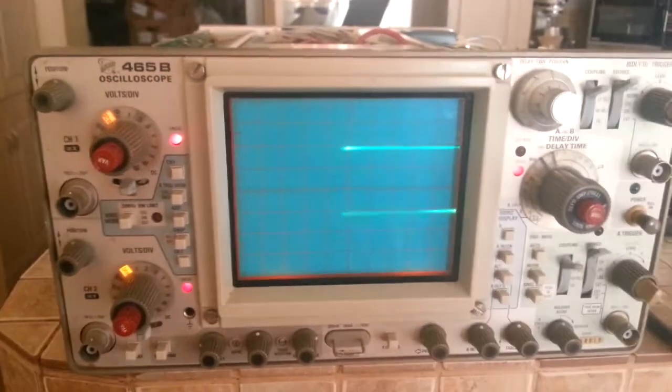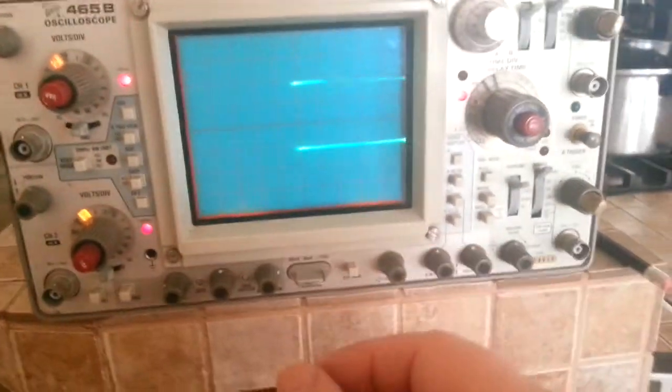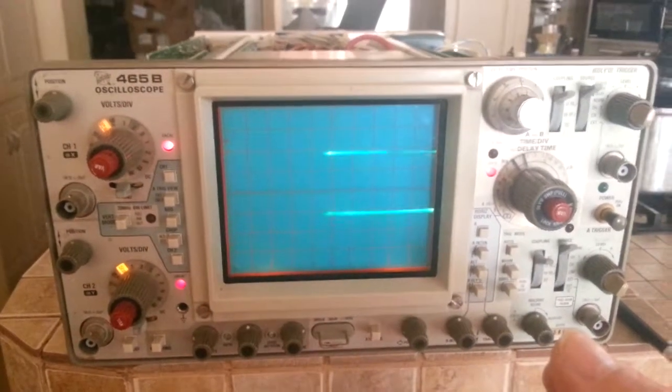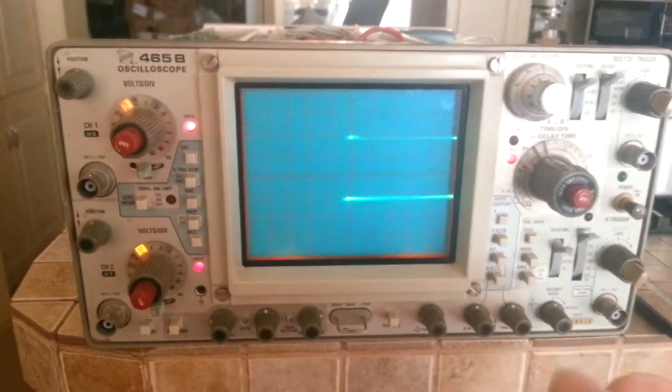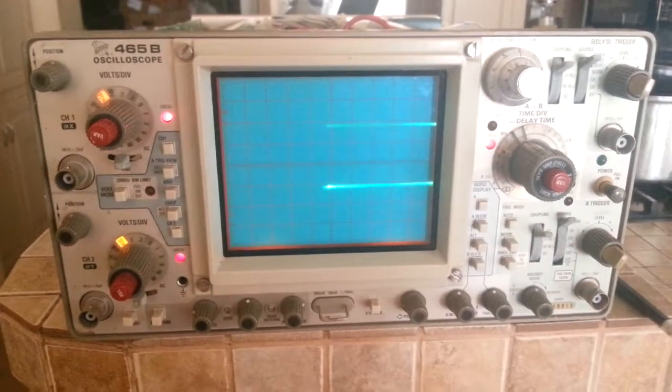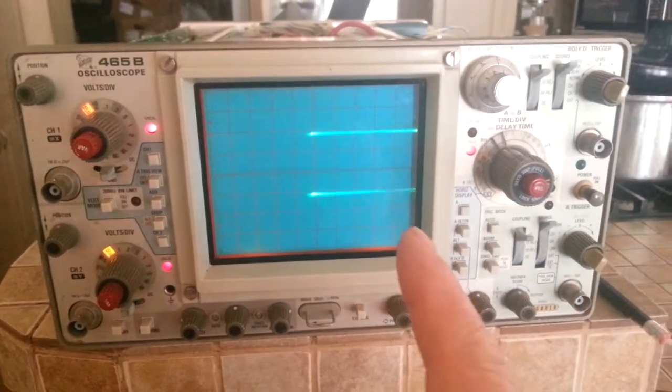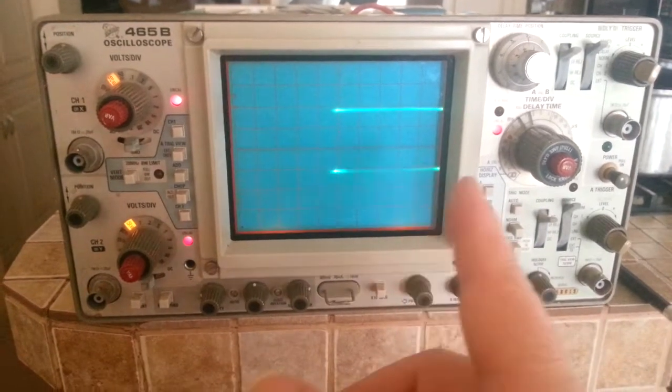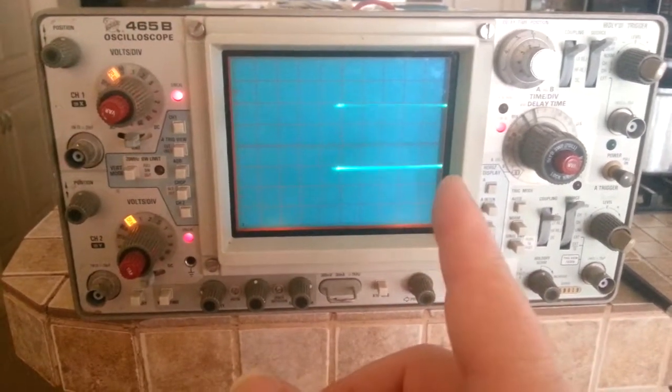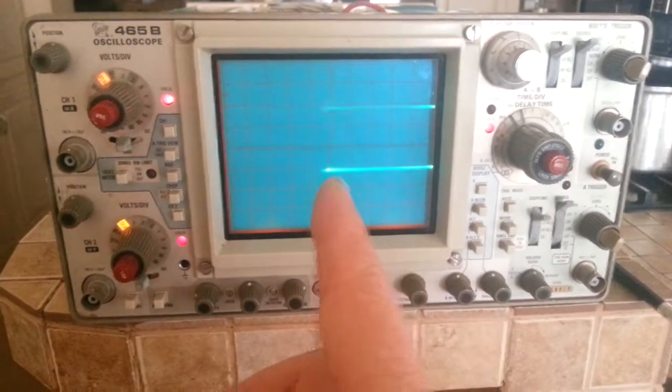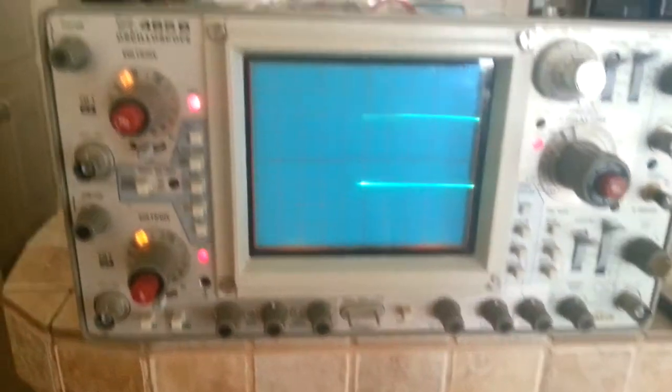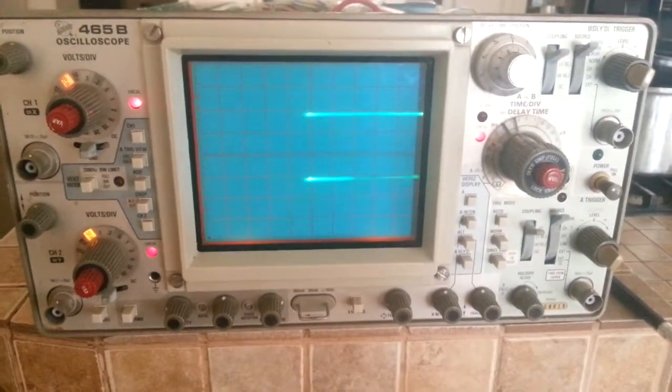My traces—if I adjust the 1x mag potentiometer underneath on the horizontal board, I can shorten these traces a little bit or lengthen them on the right-hand side. I cannot get them all the way to the left, and I cannot get them long enough to be all the way across the screen. That's the problem I'm having with this scope.